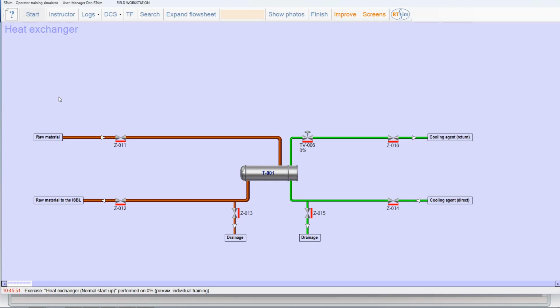Let's speak about the design of the heat exchanger. Heat exchanger condensers can be of various types, with shell and tube units being the most common. A shell and tube heat exchanger is a horizontally oriented vessel. Stream number 1, assumed to be the cold stream, starts here, enters the shell, flows through it, and exits.